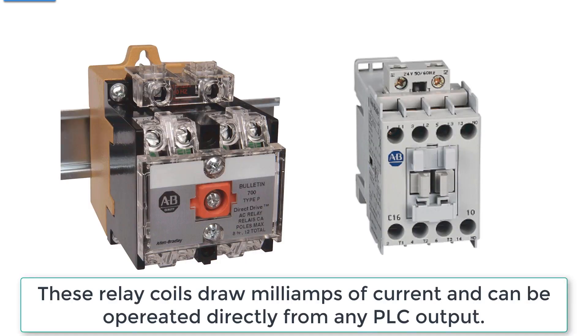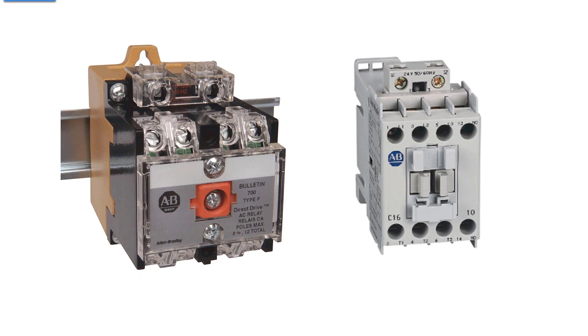For other devices, these are relays — not motor starters, just straight contactors. At the top of each one, you see where power is applied through an output from a PLC. The four large sets of contacts can be used to control electrical devices that require a lot of power, like heaters, high-power lighting, etc. If you look closely under the screw terminals, you see symbols that look like normally open contacts, indicating that all four sets of contacts on this relay are normally open.